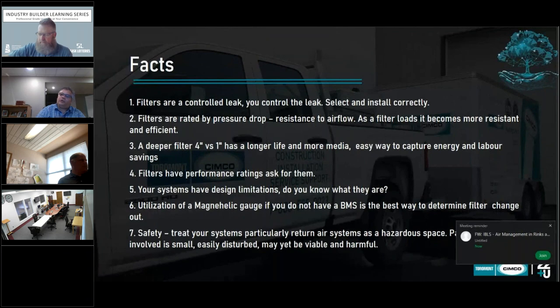You can utilize something called a Magnehelic gauge on perhaps one of your most in-demand air handlers, and that will directly translate to a performance data chart. And that will spark change out. That will instigate the need for you to address it.